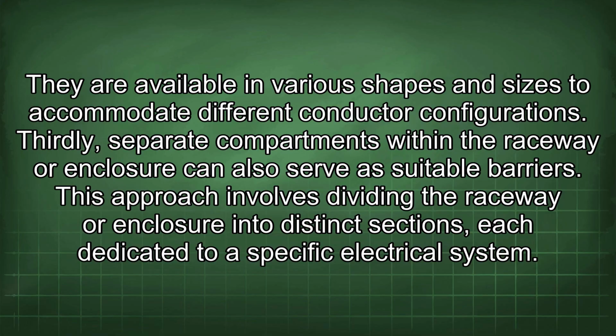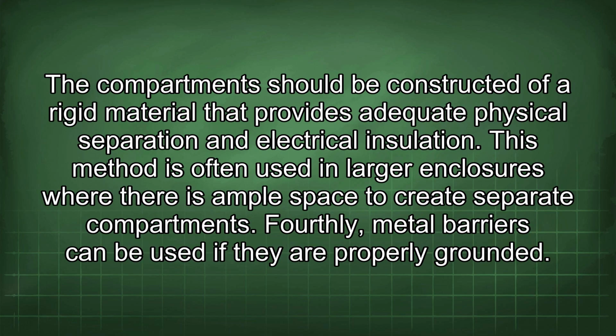Thirdly, separate compartments within the raceway or enclosure can also serve as suitable barriers. This approach involves dividing the raceway or enclosure into distinct sections, each dedicated to a specific electrical system. The compartment should be constructed of a rigid material that provides adequate physical separation and electrical insulation. This method is often used in larger enclosures where there is ample space to create separate compartments.